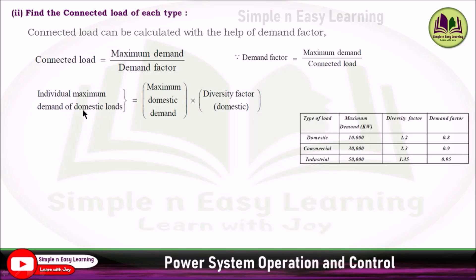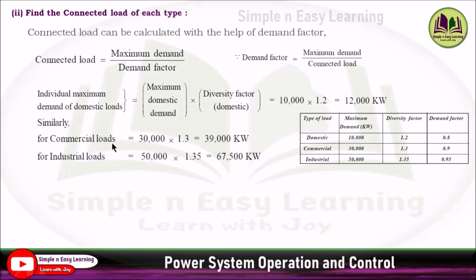Starting with domestic loads: maximum domestic demand is 10,000 multiplied by diversity factor 1.2, giving 12,000 kilowatt. Similarly, for commercial load: 30,000 multiplied by 1.3 gives 39,000 kilowatt. For industrial load: 50,000 multiplied by 1.35 gives 67,500 kilowatt. These are the individual maximum demands of each type.